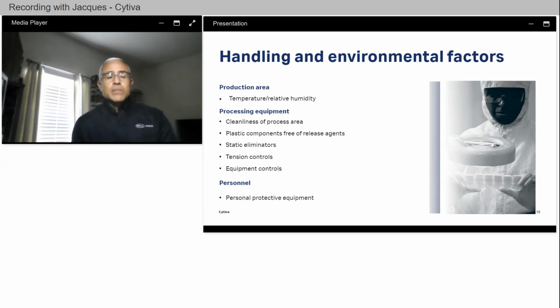Also, surrounding work areas as well as parts of production equipment which are exposed to the components of the device, from the filter membrane to the housing subassemblies, as well as the finished devices themselves, must be maintained clean and free of particulates to minimize possible sources of contamination during the assembly process. The filter housing must also be free of silicone-based mold release agents, as these agents can interfere with the sealing process and contaminate the liquid or gas to be filtered.